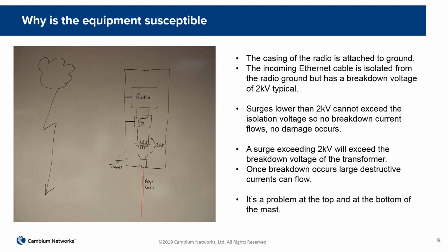And typically we would use a 2 kV surge, 2 kilovolts, applied to the drop cable with the radio itself held at ground potential. So what we know then is that, having tested that and having made sure that the isolation barrier between the primary and the secondary of the Ethernet hasn't been breached, we know that our radio is capable of withstanding 2 kilovolts, and that in a lot of cases may well be sufficient in less exposed situations.